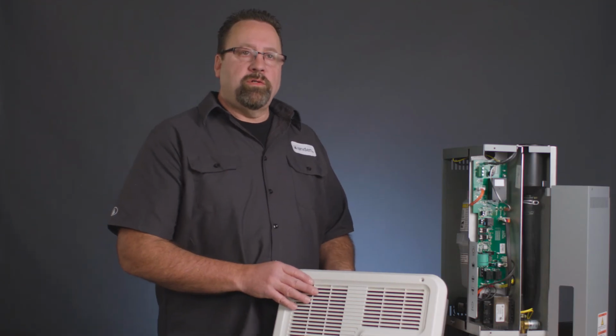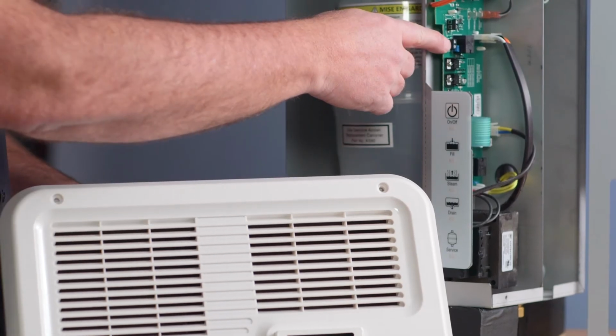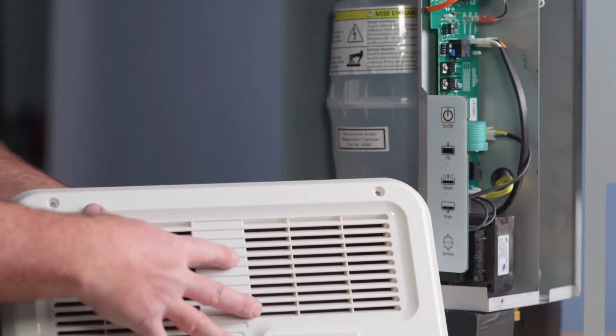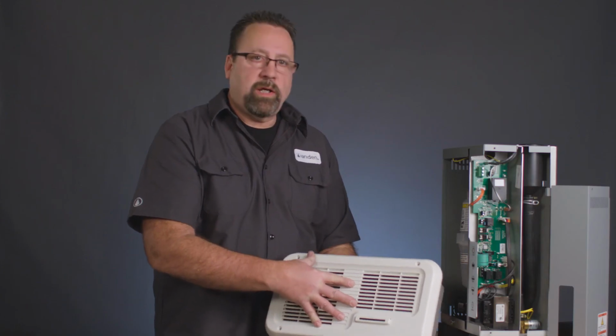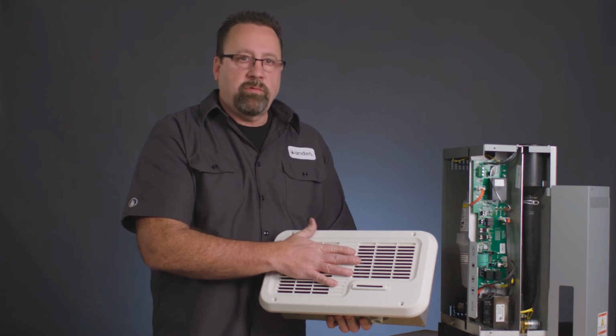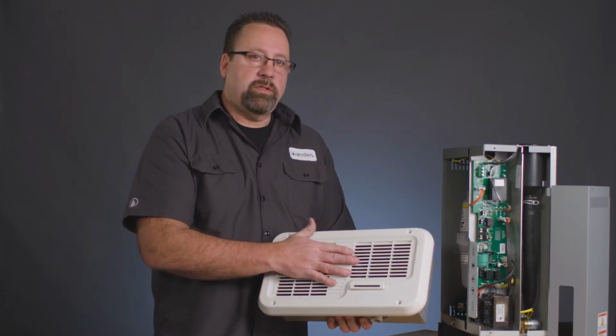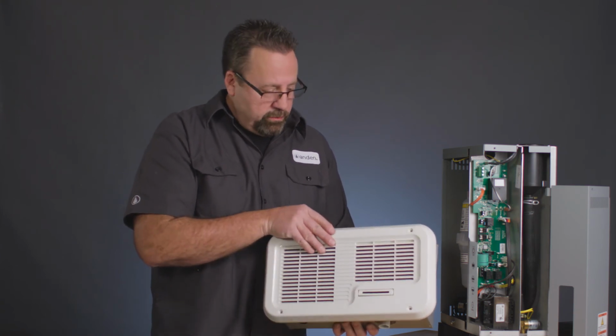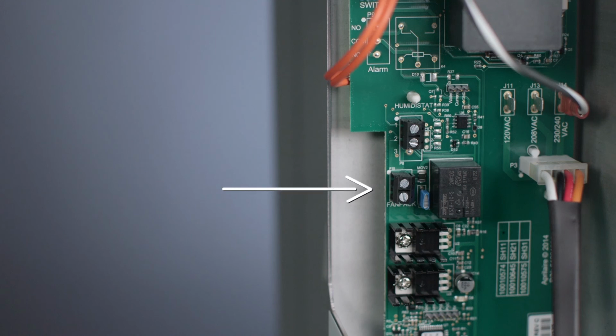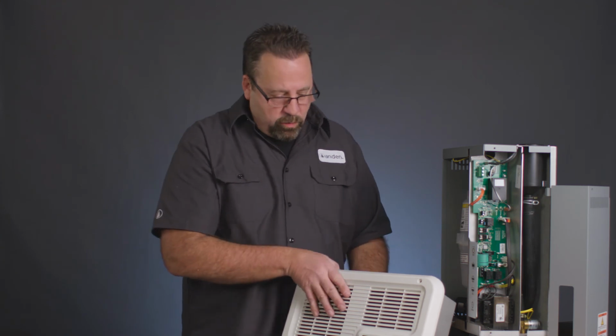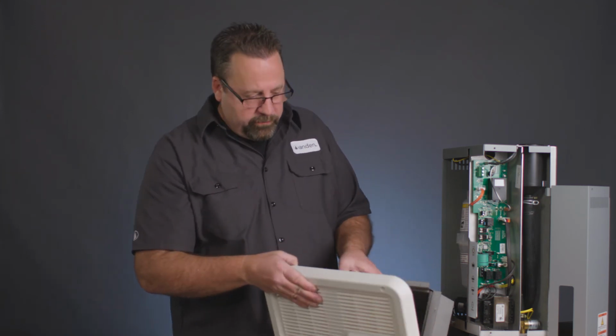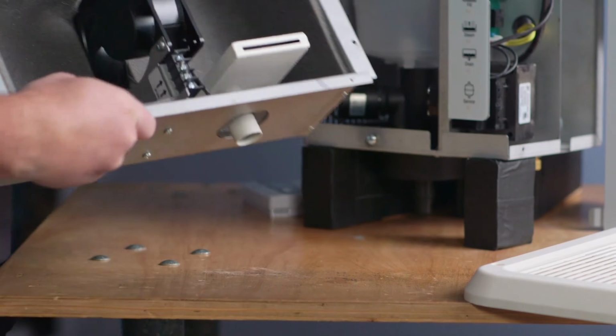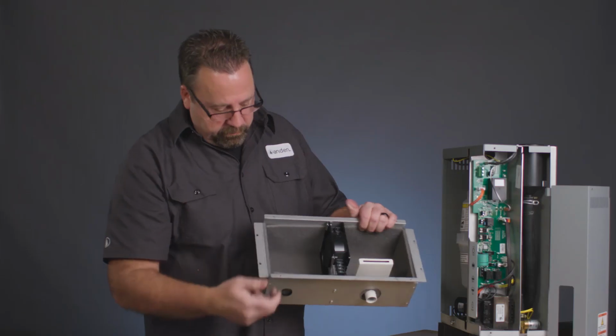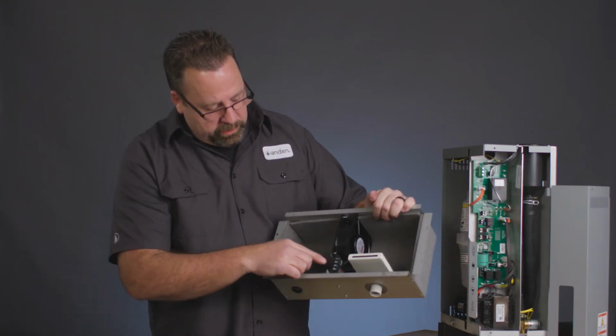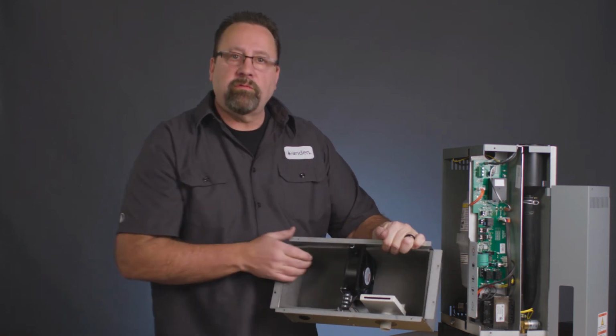When using the AS35 FP fan pack, power will go out of these 2 terminals, 24 volts, to power the fan pack, and it also keeps the fan running inside of the fan pack for an additional 4 minutes when the steam call ends to push any steam away from the unit. You'll see there are 2 terminals labeled fan pack right here. So you'll wire those with thermostat wire to the fan pack, and inside of the fan pack, you'll see the 2 terminal connections right here. Wires come in through the bottom and connect right there back to the fan pack terminals.